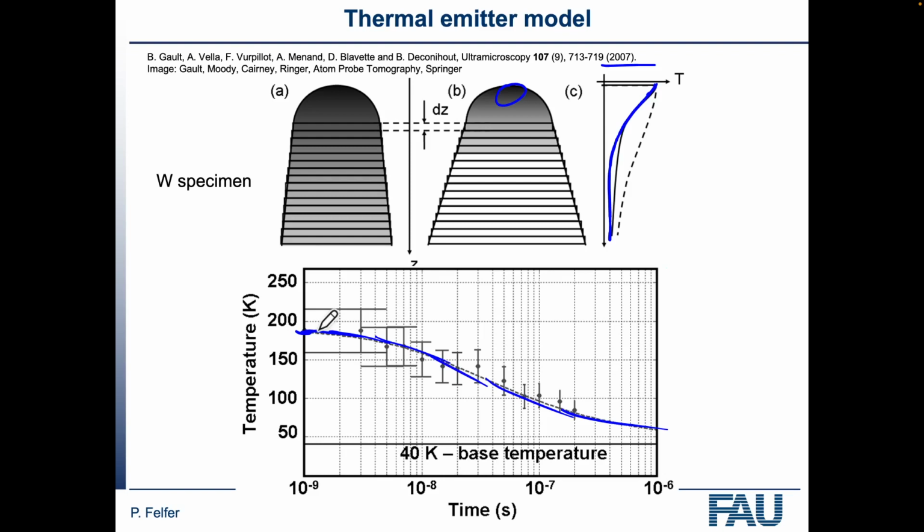And of course, that means that we can go even higher in temperature, that we will see mobility of atoms on the tip. So the higher you get in temperature, the more mobility, the more diffusion of atoms on the tip you will see. And remember, atoms actually move in gradients, in field gradients. If you remember what atom probe tips looked like, I always drew them as sort of a sphere on a cone, but in reality, they might have flatter parts, and it might be a little bit faceted because of crystallography or because of different phases and whatnot. And what it means is we have field gradients, and we have mobile atoms because they have thermal energy, which means that they can move laterally. This is sort of the downfall of laser atom probe, that we heat the specimen, and as a result, we get enhanced mobility and we get atoms moving on the surface.